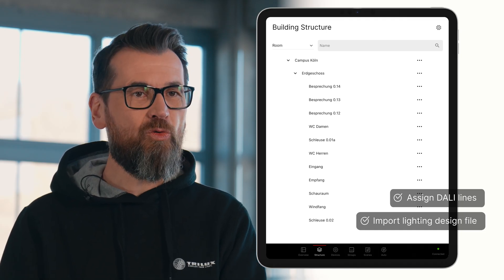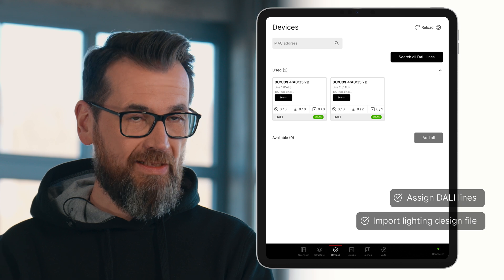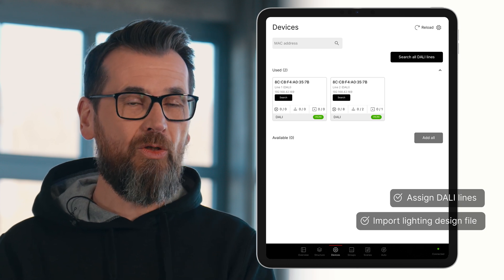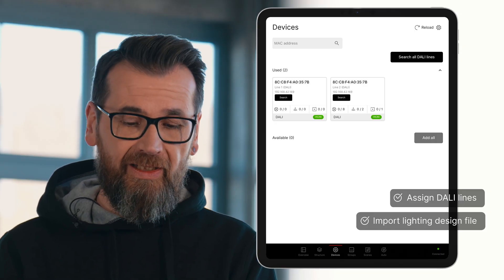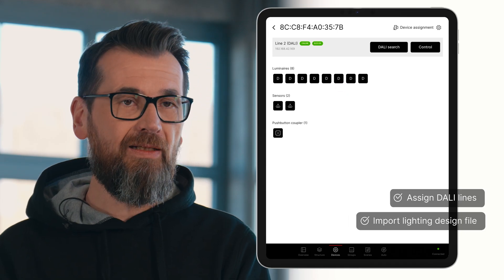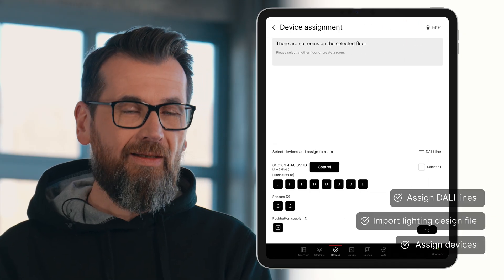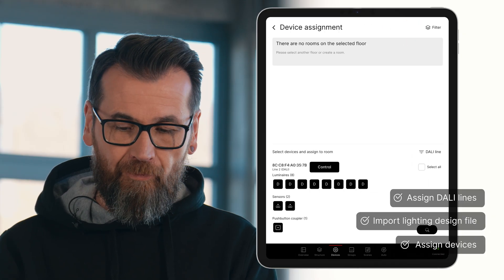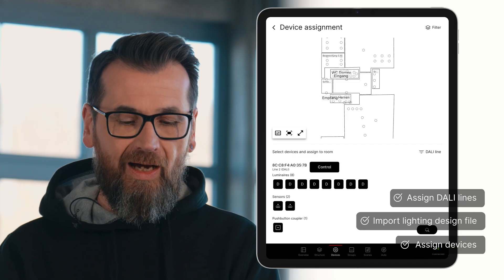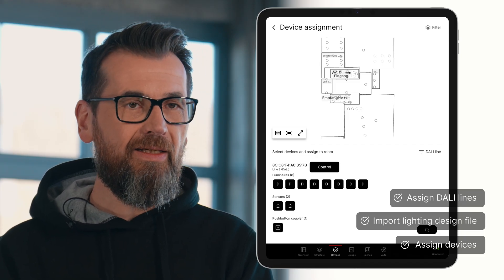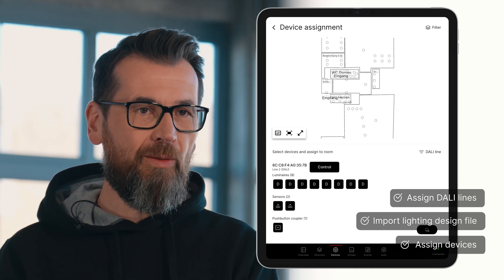In the meantime, the DALI search has most likely been completed, and we switch back to the Devices section. Here, we can see that eight luminaires, two sensors, and a push-button coupler have been found on a DALI line. To import these into the lighting plan, we select the DALI line. We then see all connected DALI devices and, via the device assignment in the top right, can add all devices into the building plan. We select the plan view and see the building plan with all luminaires, represented here by the points in the plan, and thus bring the devices from the DALI line into the building plan.